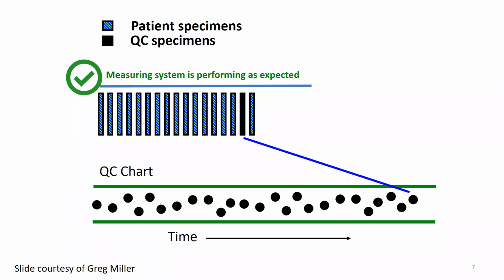QC acceptability criteria are typically based on rules that assess the standard deviation intervals for QC results. The SDIs are calculated from the observed results compared to the QC target mean and target standard deviations. QC target means and standard deviations are established during initial method validation and then refined as a result of ongoing performance monitoring. In this slide, patient samples are represented by the blue striped rectangles, and the QC material is indicated by the black rectangle. The graph below shows QC results obtained over time, with the green bars representing the limits of the acceptable range. If the measuring system is performing as expected, QC will be within the acceptable range, and we're confident in the quality of the patient results we're reporting.